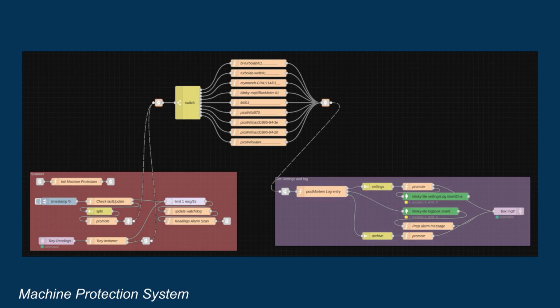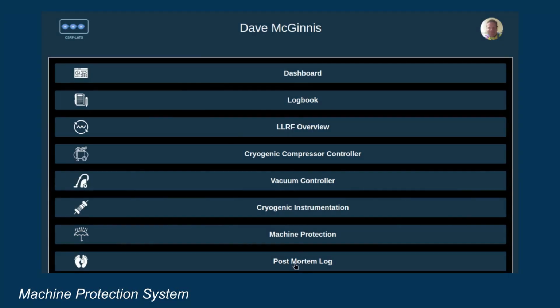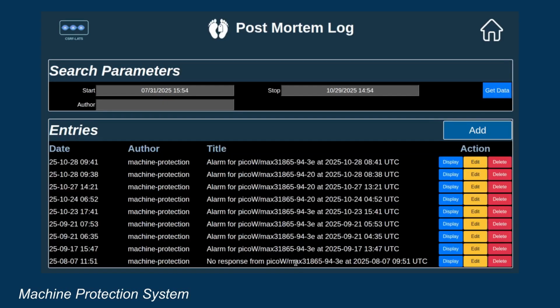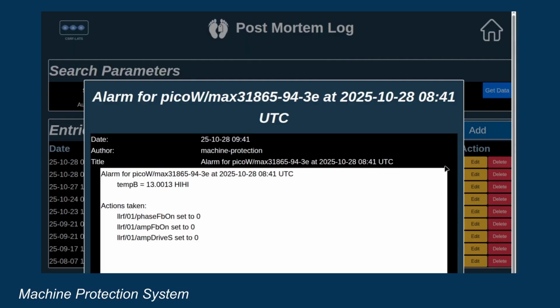documentation. In addition to sending out the actions, the settings are immediately logged, and a log entry is automatically created in the post-mortem log. This log captures not only the event, like an alarm for a temperature sensor, but also the specific actions that were taken by the machine protection system. This makes diagnostics and future analysis very straightforward.